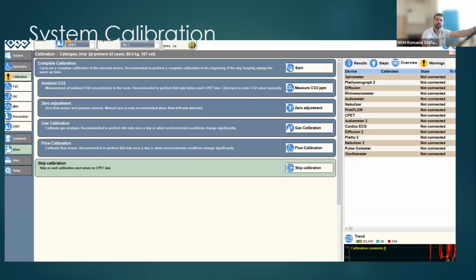And after doing these two steps, basically you start the general calibration. It's quite important that you have a ventilation system in the room where you are having the stress test, in order to ensure that the room is properly ventilated, or to have enough windows to ensure this ventilation, because all the sensors are quite sensitive, and most of the time you have difficulties in obtaining good and efficient values if you don't have enough space for the CPET and enough windows to ventilate the room. Because gas analyzers are basically prone to drift, and this could lead to serious detection errors. Fortunately, all the commercially available systems have convenient calibration procedures controlled by microprocessors.